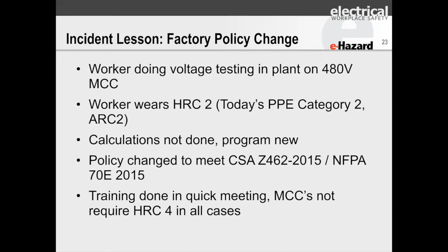The person died wearing level 2 clothing because his cotton t-shirt caught fire, burning off of him and causing severe burns, both from the shirt and the initial arc blast. When they went back and did calculations, it was over 70 calories in that motor control center. He was just doing voltage testing, which isn't supposed to be a major concern, but it arced because of a slip -- that kind of thing happens. So it's really important that when you have policy changes or see a hole in your program, you fix it quickly and communicate thoroughly to all workers.